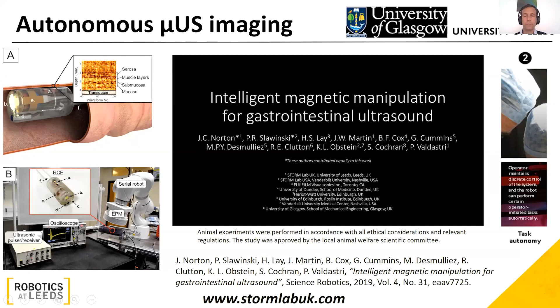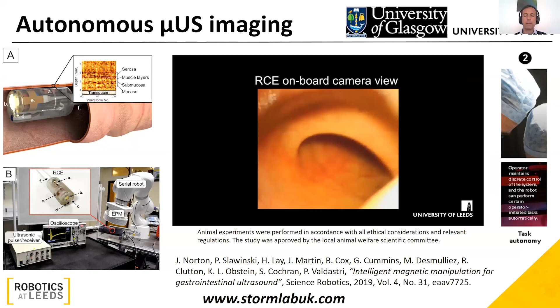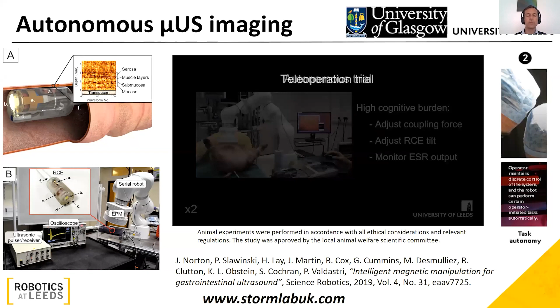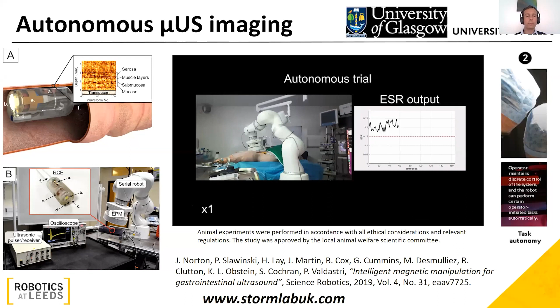Once we were satisfied with bench trial, we moved to a porcine animal model for validation. First, we reached a desired position in the colon by magnetic navigation, and then we tried to acquire a micro-ultrasound image via manual teleoperation of the external magnet with very scarce results. Then we tried the autonomous routine based on real-time localization and ultrasound signal strength. And with this computer-assisted approach, we were able to acquire a clear image of the mucosa layer, demonstrating for the first time how intelligent magnetic manipulation can enable the acquisition of micro-ultrasound images from regions deep inside the body with a flexible probe.